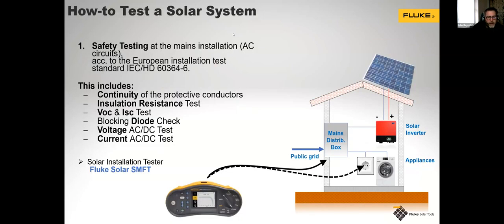So, firstly, this graphic will change slightly as we move on. The first thing we need to do is safety testing at the AC side, and that will be tested to the test standard of 60364-6. Those tests will include, but are not completely restricted to, continuity of the protective conductors, insulation resistance, VOC and ISC test, blocking diode check, voltage AC and DC, and current AC and DC. And we've got one tester that will do all of that, and that's the Fluke Solar SMFT. But again, because it is on the AC side, certainly in a residential property, you have got other products that you may already own that can do that.